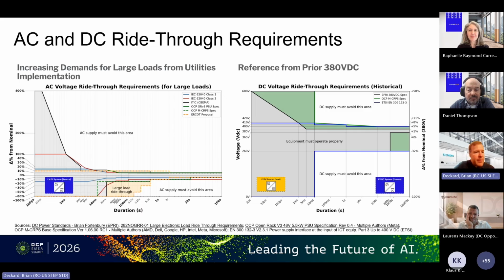Moving from there, one of the interesting dynamics coming rapidly into the regulation scene is large load ride-through requirements. As you can see, this is taking what has traditionally been double-digit milliseconds into triple-digit milliseconds and beyond for large load ride-throughs. Why does that matter?